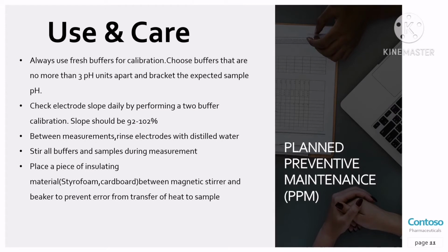Planned preventive maintenance for magnetic stirrer. First point, always use fresh buffer for calibration. Choose buffers that are no more than 3 pH units apart and bracket expected sample pH. Check electrode slope daily by performing a 2-buffer calibration. Slope should be 92 to 102%. Between measurements, rinse electrode with distilled water. Stir both buffer and sample during measurement. Place a piece of insulating material, styrofoam or cardboard, between magnetic stirrer and beaker to prevent error from transfer of heat to sample.